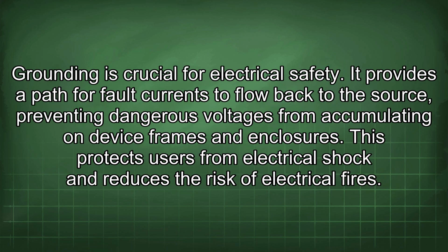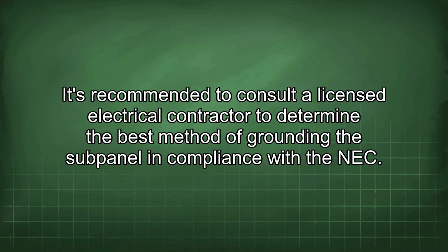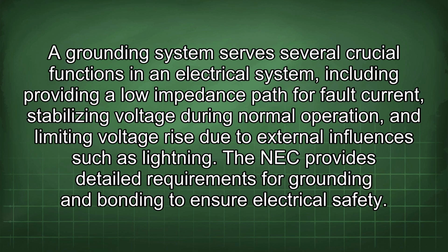Grounding is crucial for electrical safety. It provides a path for fault currents to flow back to the source, preventing dangerous voltages from accumulating on device frames and enclosures. This protects users from electrical shock and reduces the risk of electrical fires. It's recommended to consult a licensed electrical contractor to determine the best method of grounding the subpanel in compliance with the NEC. A grounding system serves several crucial functions in an electrical system, including providing a low impedance path for fault current, stabilizing voltage during normal operation, and limiting voltage rise due to external influences such as lightning. The NEC provides detailed requirements for grounding and bonding to ensure electrical safety.